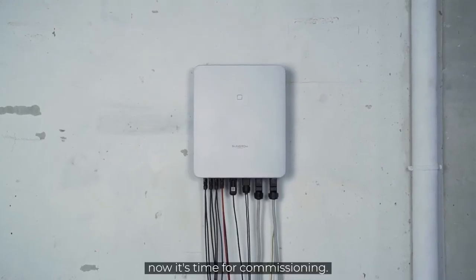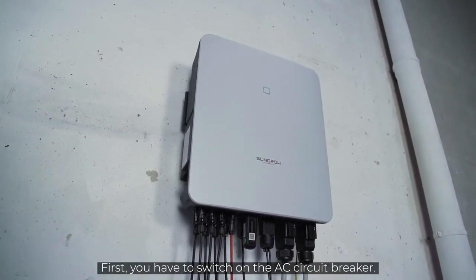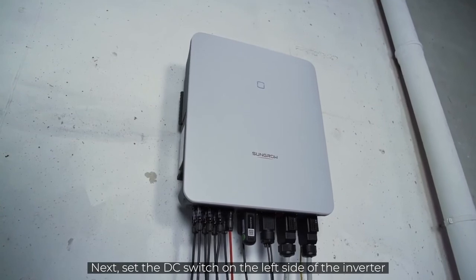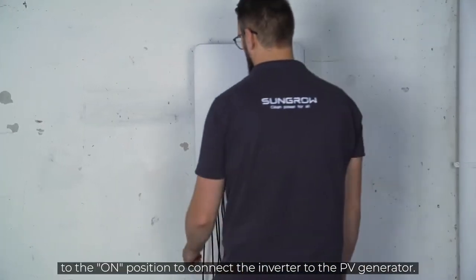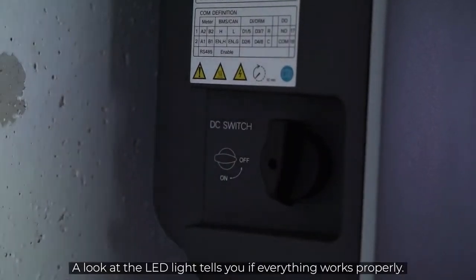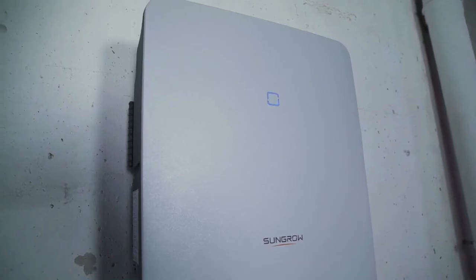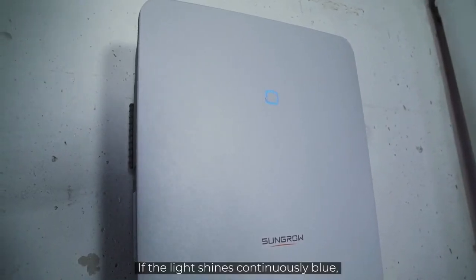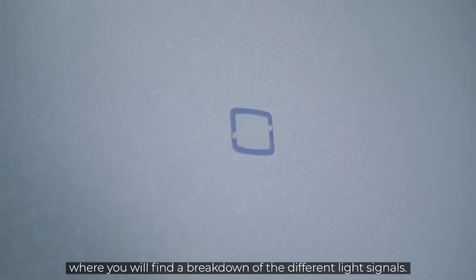First, you have to switch on the AC circuit breaker. Next, set the DC switch on the left side of the inverter to the ON position to connect the inverter to the PV generator. A look at the LED light tells you if everything works properly. If the light shines continuously blue, the inverter is ready for use. If this is not the case, please refer to the manual where you will find a breakdown of the different light signals.